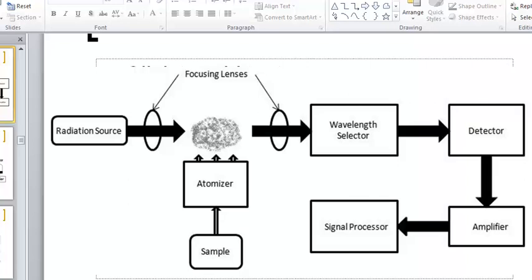That light bulb goes into the flame. And that's what you're seeing here as basically this cloud. And we know now that it's drawn as a cloud because we're looking for free atoms. We need the atoms out of the solvent. And that's the purpose of what we call the atomizer. So the sample gets sucked up through the nebulizer tube, which is that piece of plastic. The nebulizer takes the solvent, breaks it down into really fine droplets, and then it changes it into a mist. And that mist is what's given to the flame.